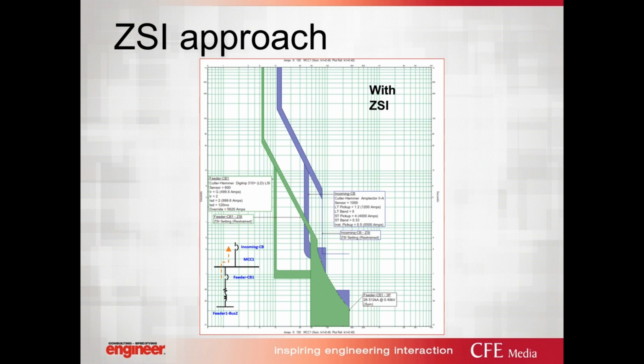Now, let's continue. By utilizing ZSI, we can control the incoming breaker. We can enable the circuit breaker instantaneous, and at the same time, a restraint signal from the load circuit breaker ensures that we are okay on the incoming breaker instantaneous. Therefore, the instantaneous portion of the incoming breaker is now enabled, since the restraint signal from the load circuit breaker prevents instantaneous tripping on the incoming breaker by almost, I put it at, 250 milliseconds. Therefore, let's see the result.